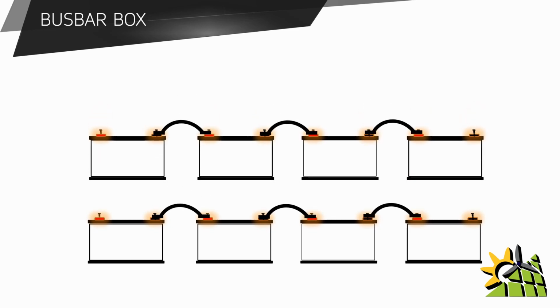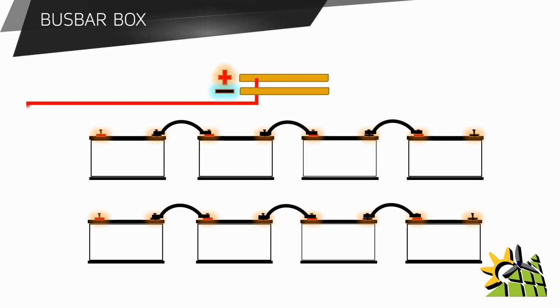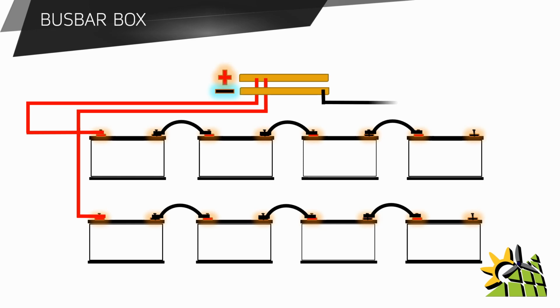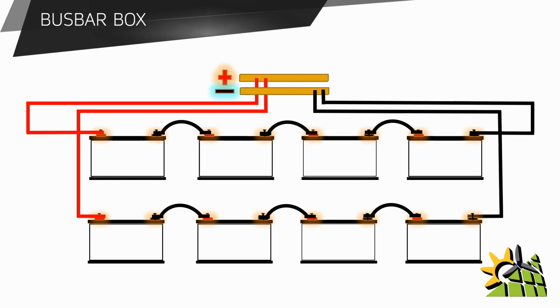So in the busbar box, you would have a positive busbar and a negative busbar. The positive cable would be connected to the first battery bank's positive pole, and the same length positive cable would then also go to the second battery bank's positive pole. A negative cable would go to the negative pole of the first battery bank, and the same length negative cable would go to the second battery bank's negative pole.